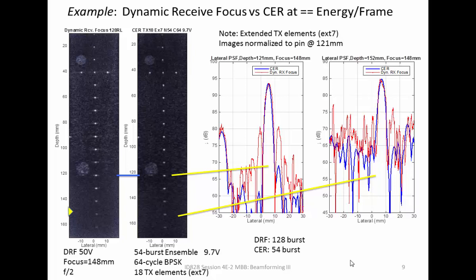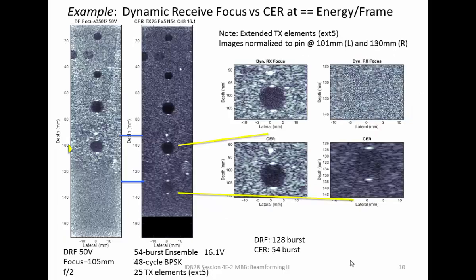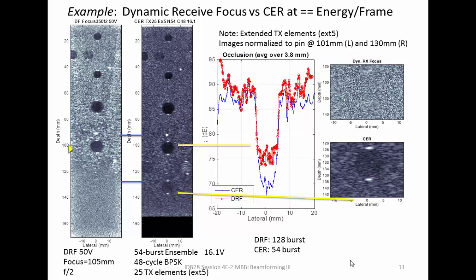We see at least 20 dB suppression of side lobes compared to dynamic receive focus. Looking at a phantom image, comparing dynamic focus to coded excitation reconstruction, we get about 6 dB better contrast resolution inside the void. And the dynamic focus doesn't even pick up a deeper void at all. Comparing to synthetic transmit aperture with conventional pulses, in the near field we get the same main lobe response, confirming it focuses everywhere as synthetic transmit aperture should.